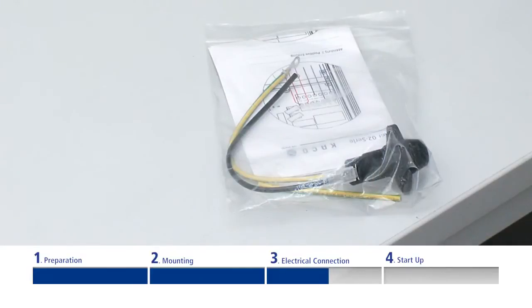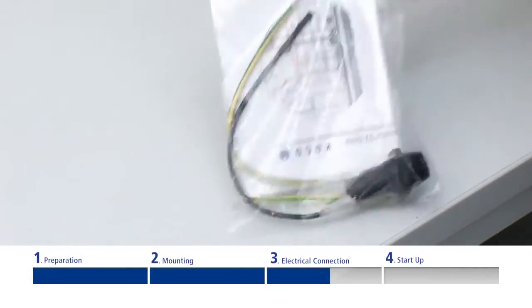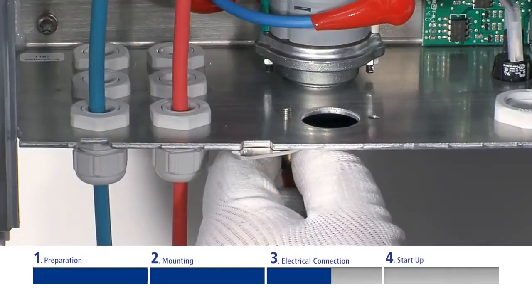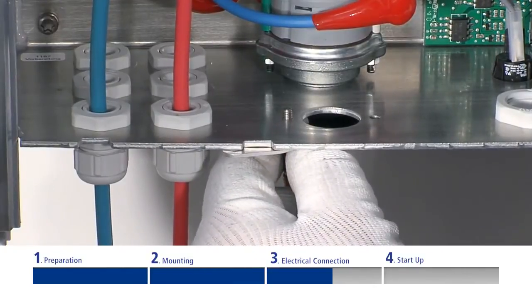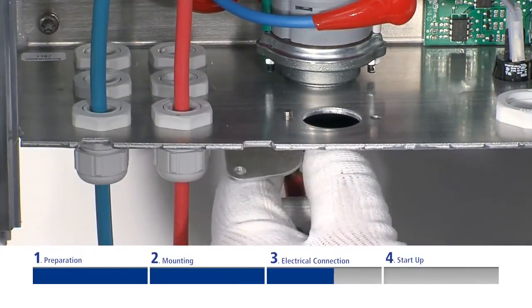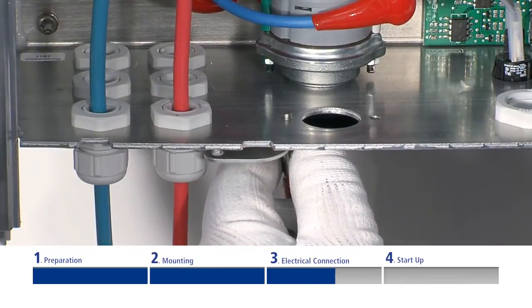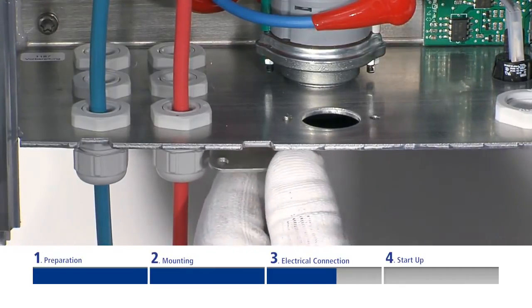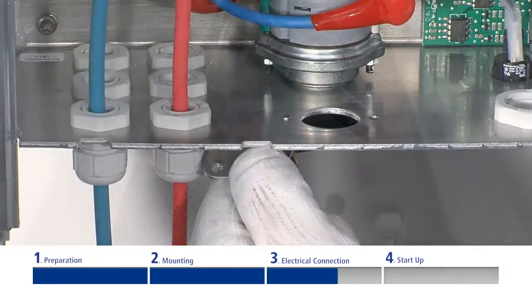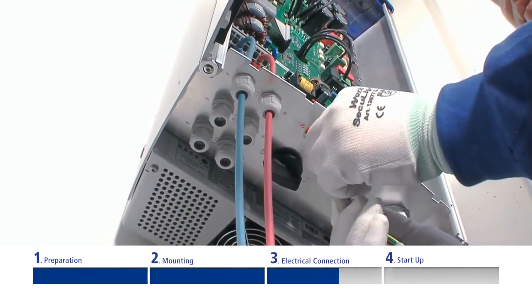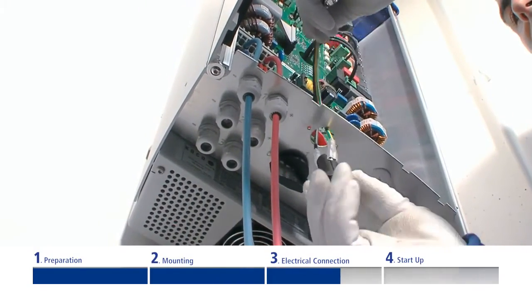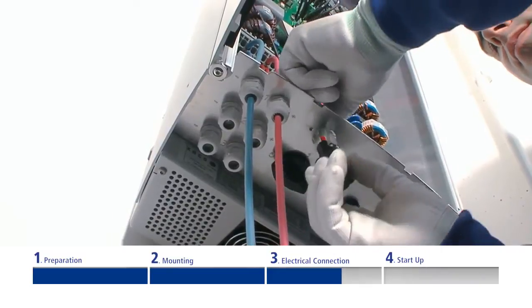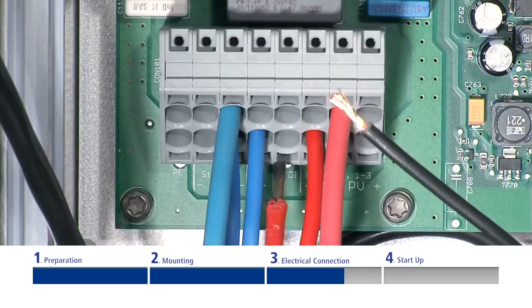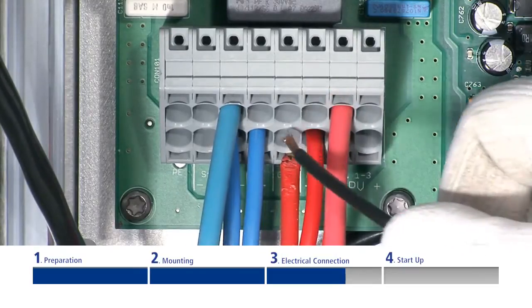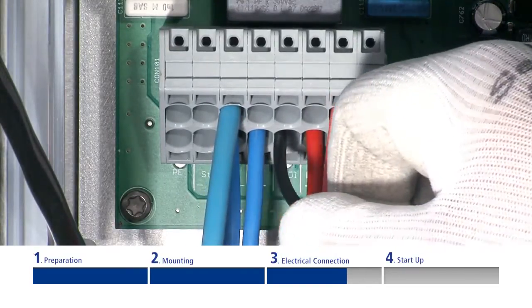Some module manufacturers, especially those of thin film modules, stipulate earthing on the generator side. An optional earthing kit for use on galvanically isolated powador inverters is available for this purpose. Use a screwdriver to remove the cover of the fuse holder and attach the fuse holder using the screws provided. Connect the black cable to the bottom DC terminal labeled GFDI.